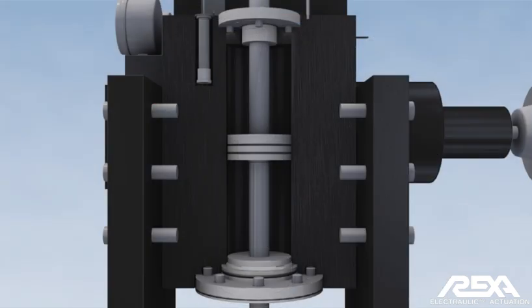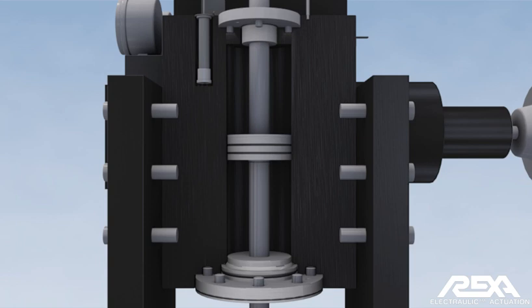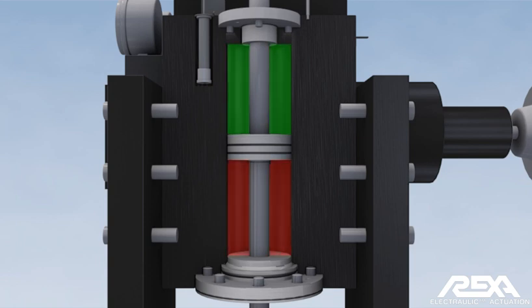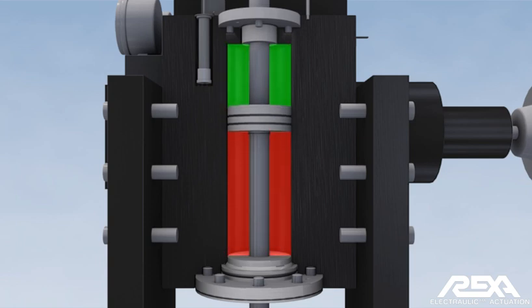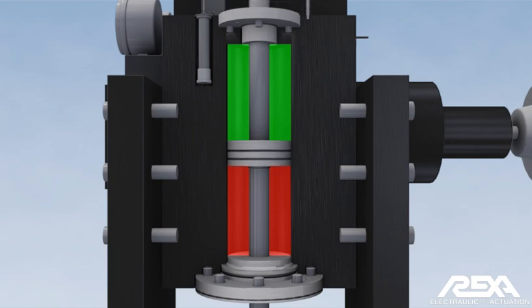The actuator is a double-shaft cylinder design, meaning that the shaft goes through the middle of the piston, maintaining the same area on each side of the piston. This configuration results in the same volume of oil pumped to either side to position it, eliminating the need for any extra oil storage.